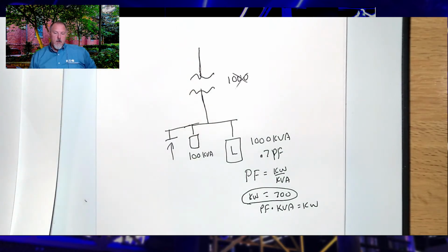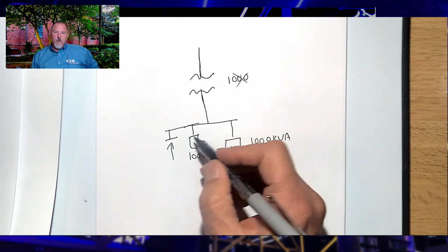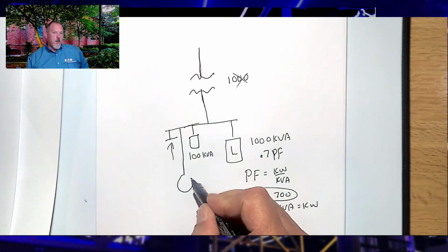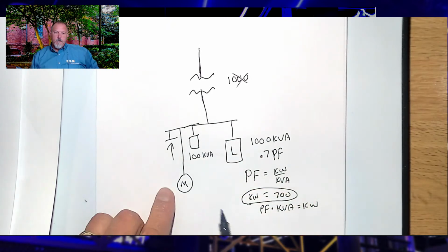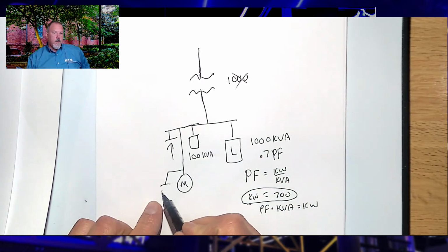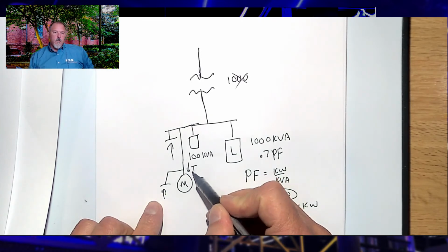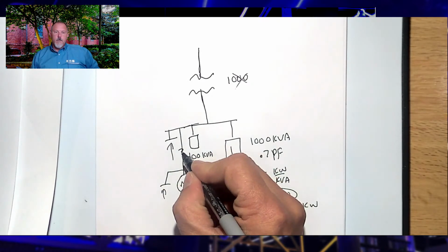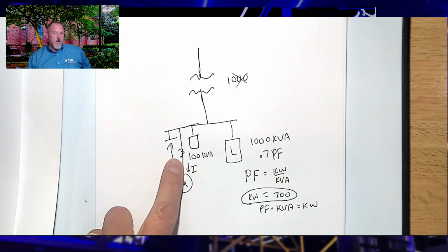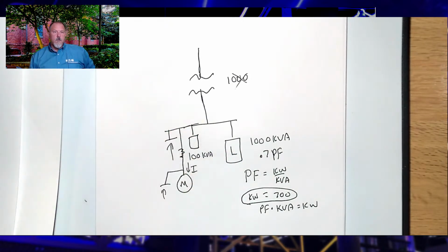So the utility wants me to fix that, and he's exactly right that we would potentially get a power factor penalty. And if you avoid $2,000 a month, you can save a lot of money. But what you're not saving is actual watts. With a little bit of an exception: if you had, let's say, a motor way down here, and I reduce my current by hanging a capacitor down here, then my I squared R losses along that line, I could basically save. So that is exactly right.